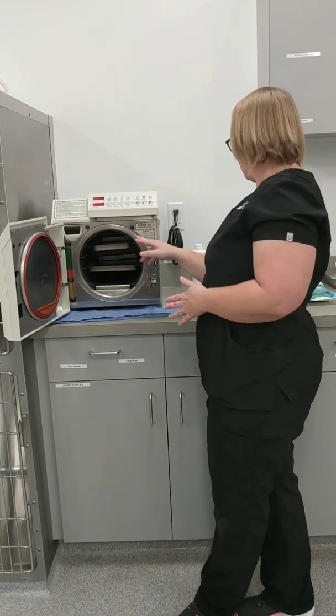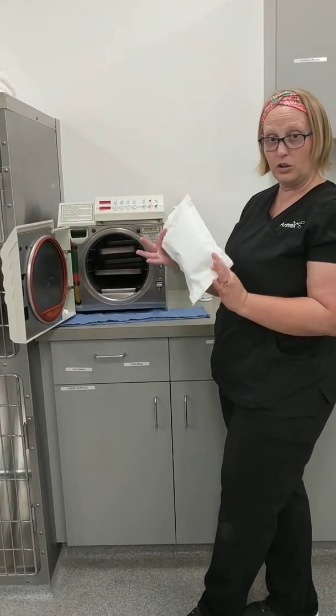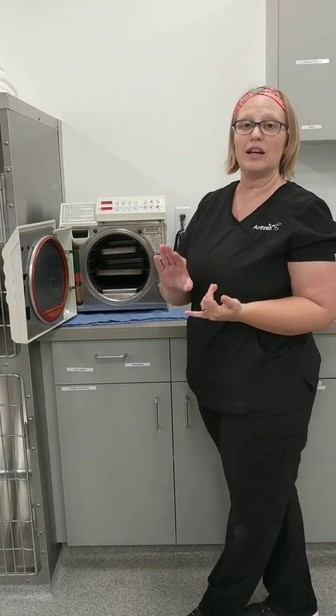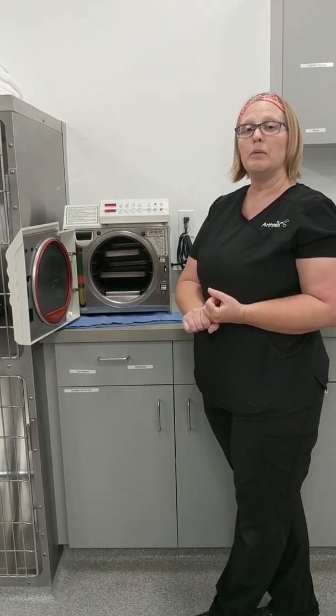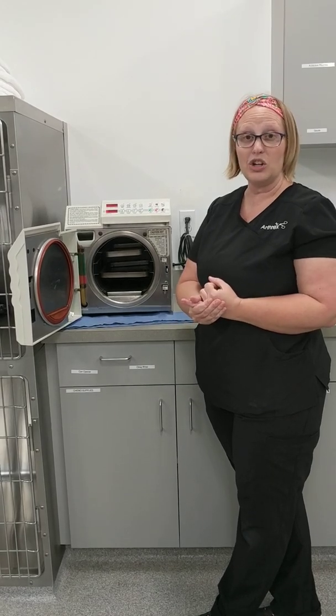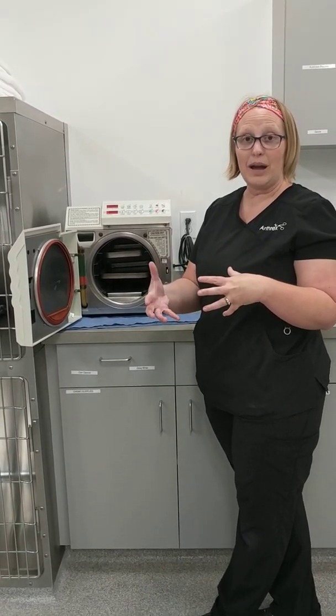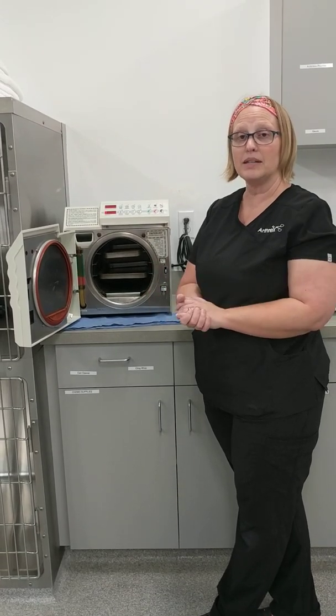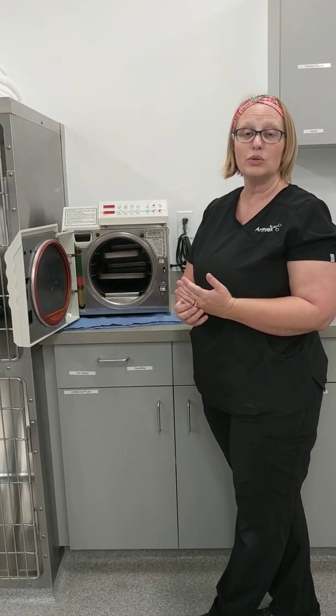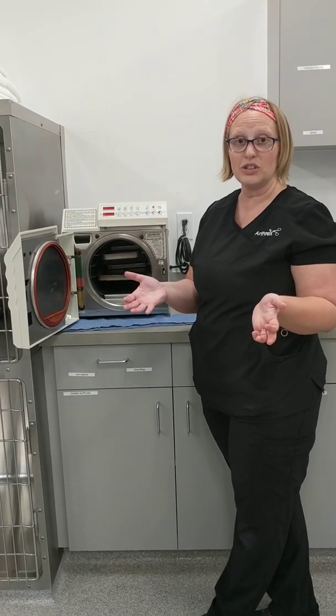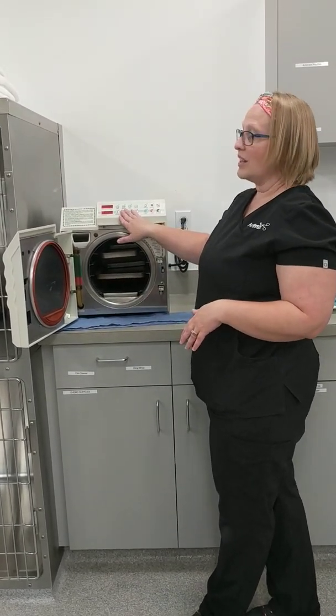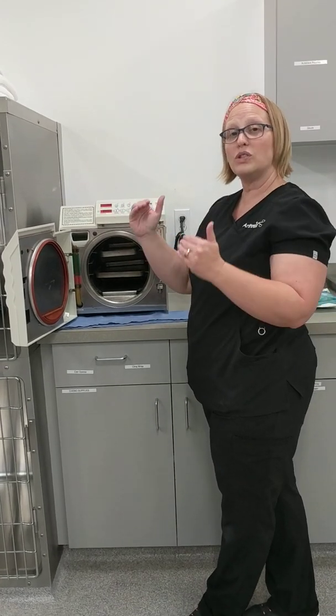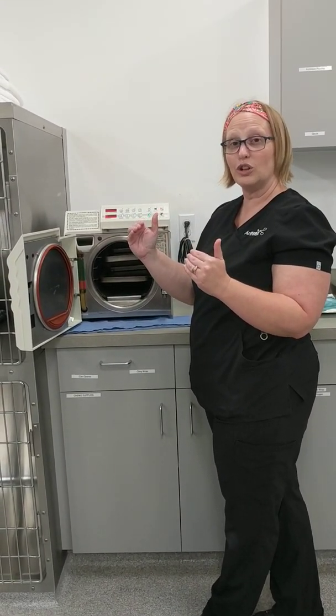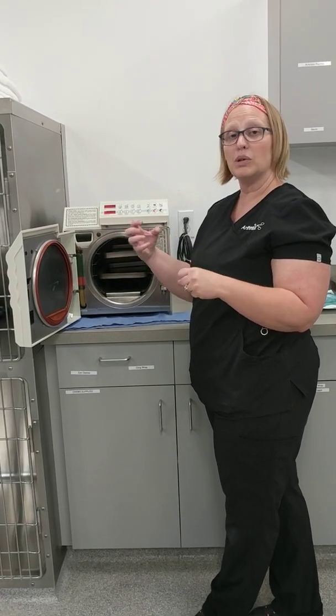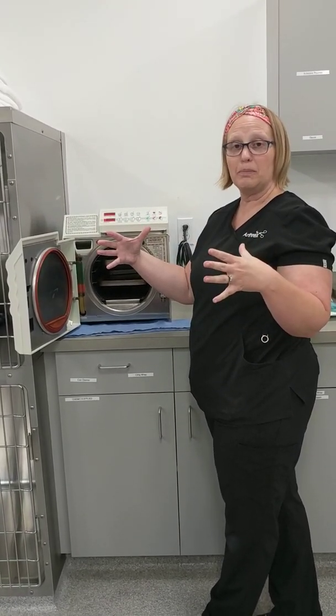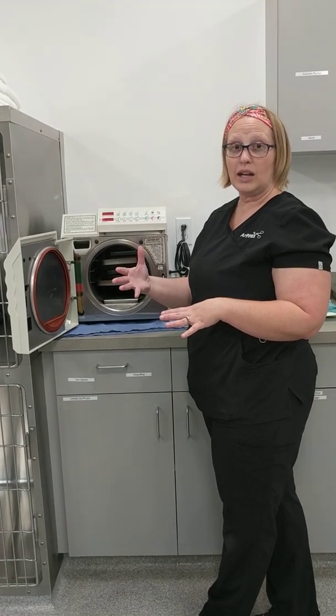As far as pouches go, this is a good example of a pouch. We're going to be autoclaving a pouch today. Pouches can be anything that are plastic or paper wrap. These things don't stay sterile for as long as, say, a fabric multi-wrap, but they are sterilized for short-term sterilization used for surgical procedures as well. When you hit your pouch setting, this again goes to about 270, but it holds that heat temperature and that steam temperature for a little longer, so for about 5 minutes before it releases that constant pressure steam and then allows the cooling process to start again.